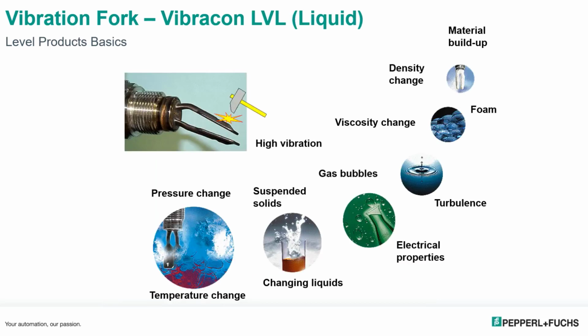As well as buildup, you could have corrosion on the forks. So even with loss of metal, though it's vibrating at a certain frequency, we're still able to see that differential vibration and give an accurate output. According to this, with all of these types of corrosion on the probes, these probes will still work. The Vibracons are pretty hardy probes. They can be damaged. You can bend the forks. We don't suggest that, but they can be bent and still work.